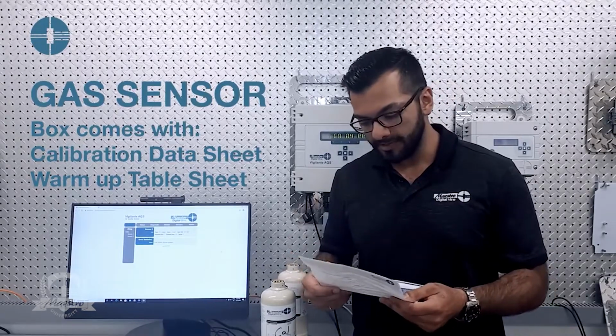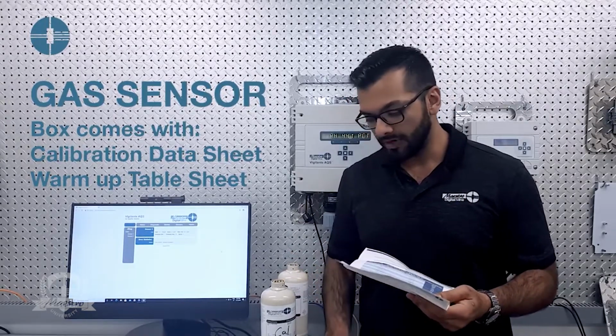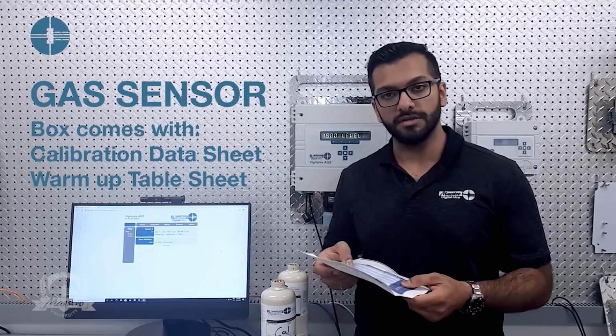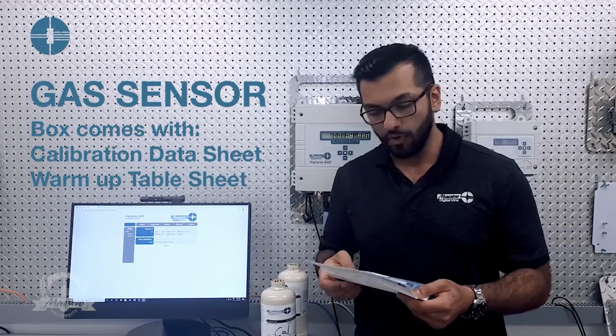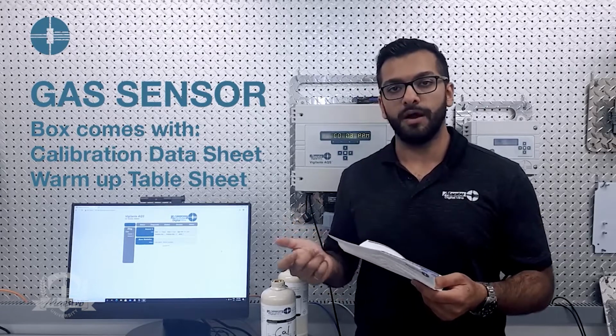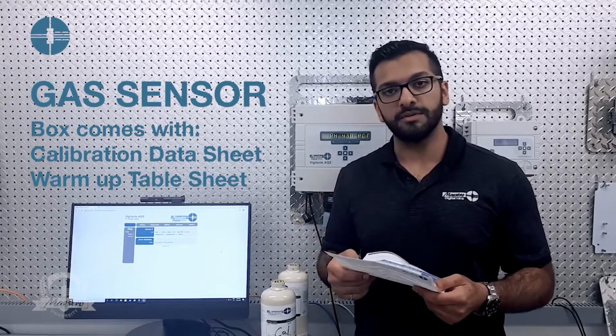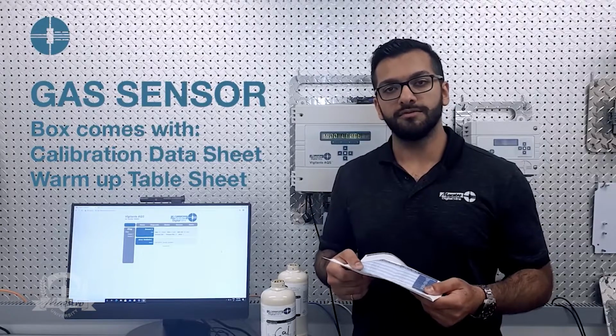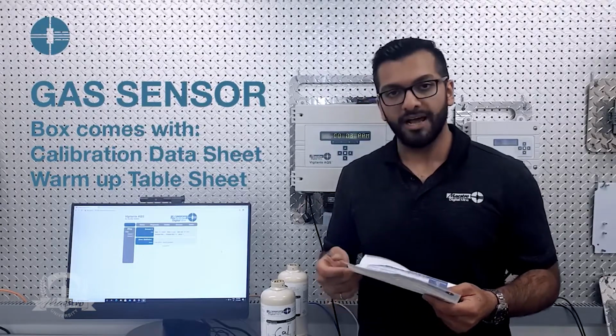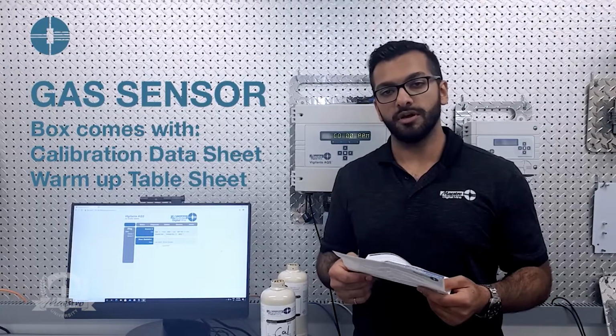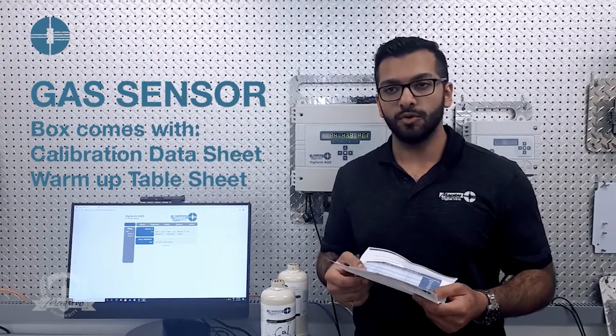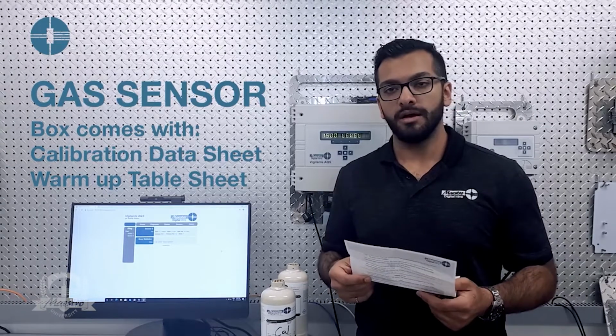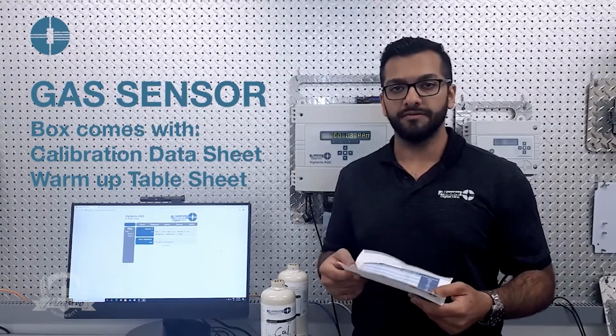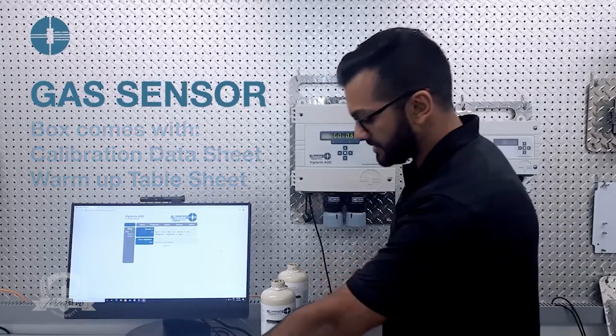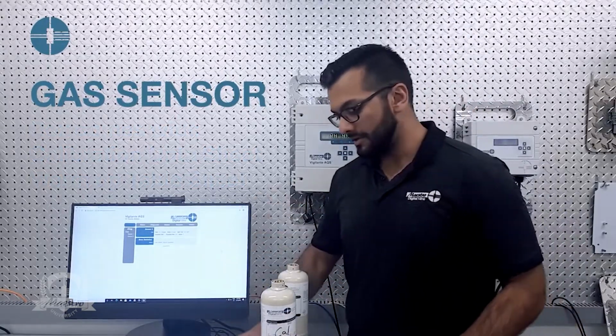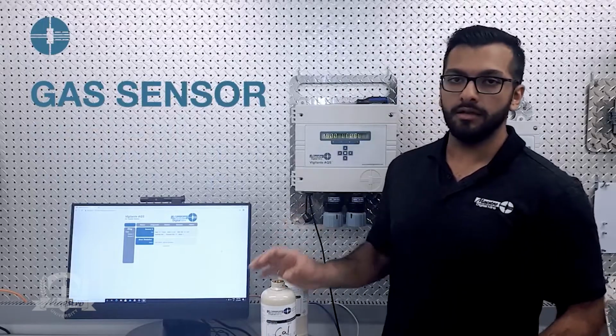So here in the warm-up table, the first thing you can look at is what type of sensor you have, and then you can reference it on the warm-up table to know how long you need to allow the sensor to remain powered on before you can actually attempt a calibration, or use it in the field. Because during the warm-up time, the sensor will not display any readings. So it's important to note how long your sensor will be warming up before attempting calibration or using it in the field.